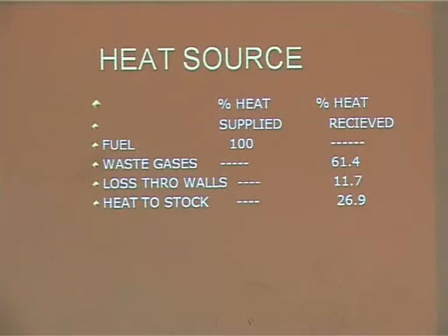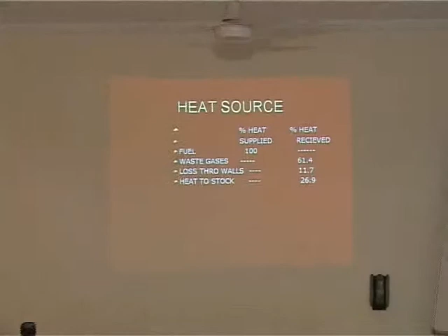So it is seen from the above that a major chunk of the input heat is lost through the waste gases. As you can see from this, waste gases take away most of the heat of the furnace. As the heat lost to the walls and refractories will not change for the given furnace, all the recovered heat would be available to heat the charge, if you can take that heat back and reuse it for your furnaces. The heat is recovered by means of what you call recuperators. So these are heat exchangers which are used for preheating the combustion air before it enters your furnace. Now heat content of air in BTUs per cubic foot at various temperatures is given in this chart.